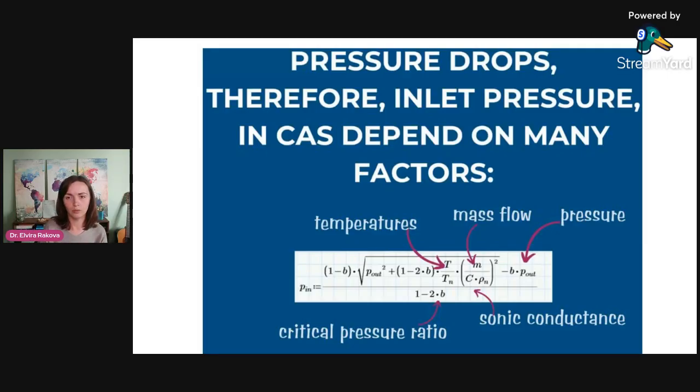Just think about the pressure drops and in general, where it is extremely important to calculate the correct sizing of the pipe. And for the pipe, the pressure drop, it's not the Darcy-Weisbach, it's not just one single diameter calculations thing. There is no one formula. You have to calculate always the C value for the pipe in compressed air, and always B value for the pipe. I think we had our first coffee in compressed air where I showed the equations. And if you have questions, I can show you more equations about this.